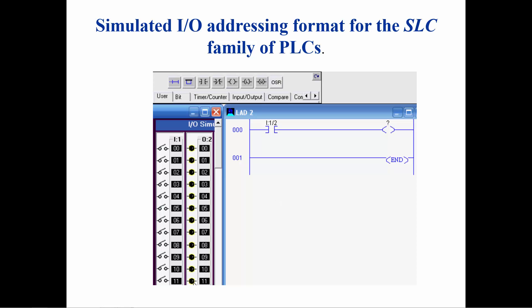Then you would grab the address of an output and drag it to the coil instruction. The address O colon 2 slash 11 refers to the 11th connection on the output module in slot 2.